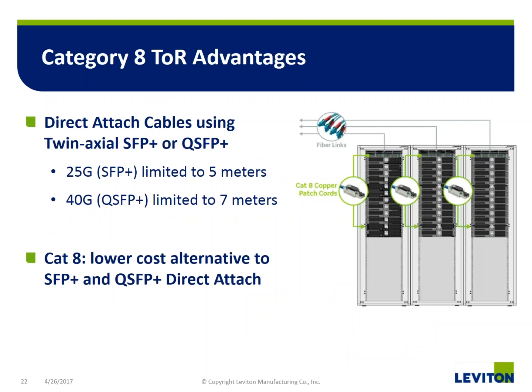Let's look at Category 8 top-of-rack advantages. Compared to the direct attached cabling using twin axial, you're limited to 25G at 5 meters, 40G at 7 meters. We believe Cat 8 is going to be a lower cost alternative. Some of these direct attached cables with the SFP type of interfaces can be quite expensive, whereas with Category 8, it's basically a patch cord. It's the same advantage that Category 6A has had compared to the 10G SFP type of cable.